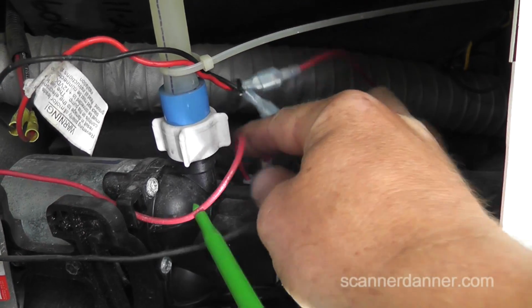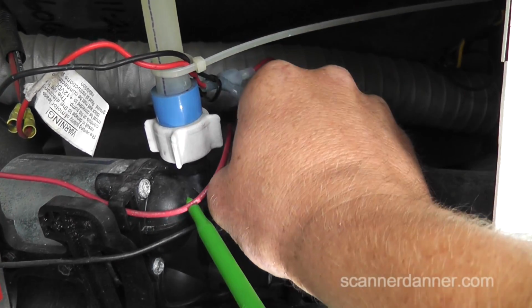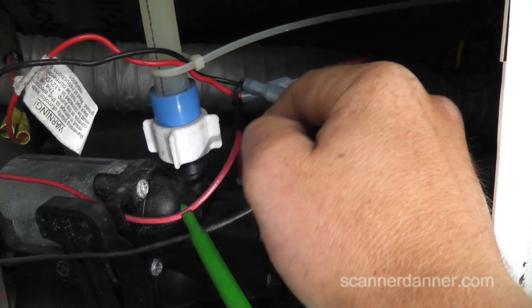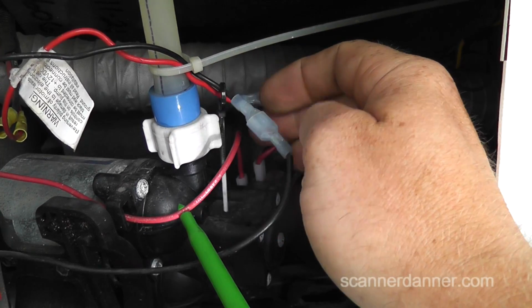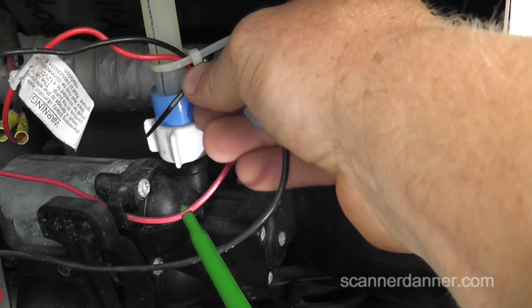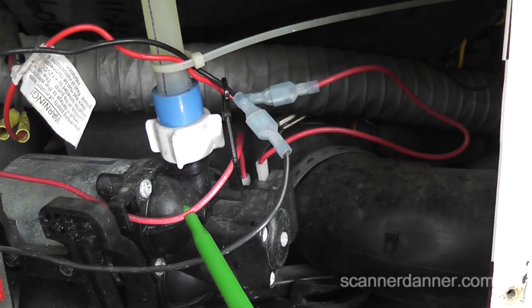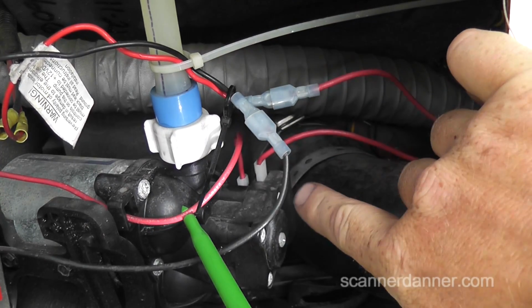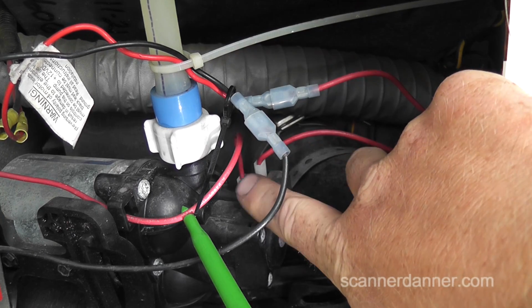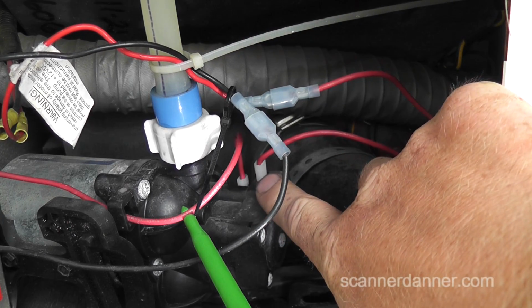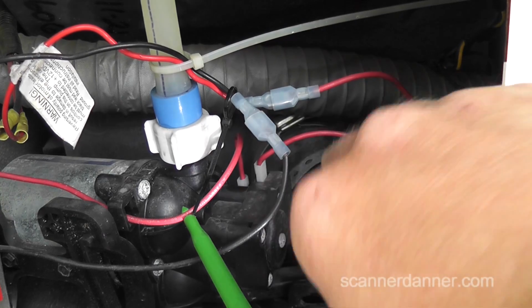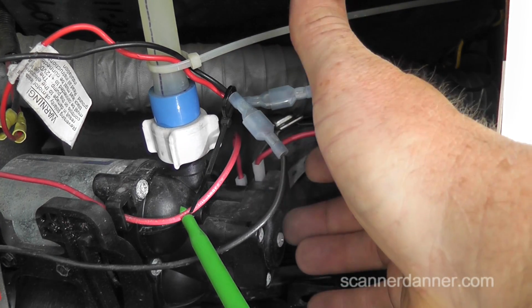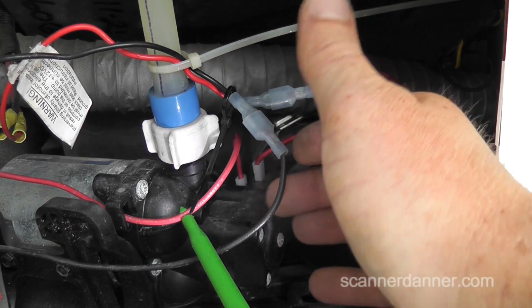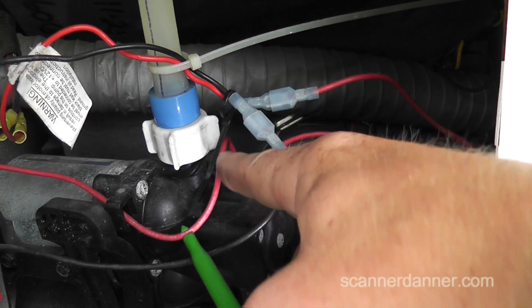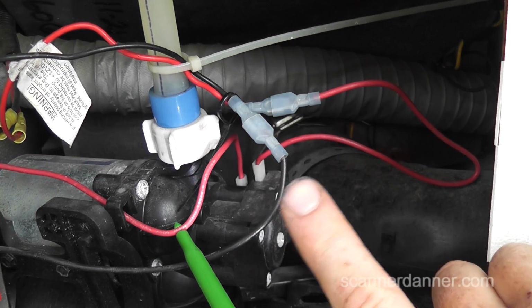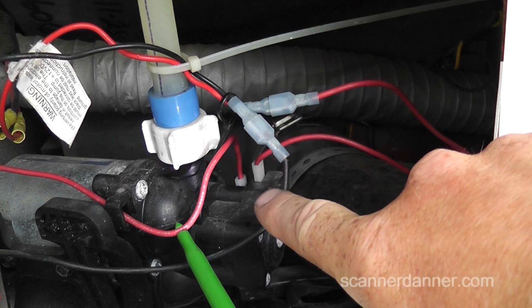When you have issues like this, let's disconnect this wire. What ends up happening, guys, is even though that's annoying, even though I'm stressing and pushing on these pins, it looks like a bad connection there. It actually very well could be the contact inside of this pressure switch, that when I'm pushing on the terminal ends, I'm actually moving and stressing the male pin that's inside of that.